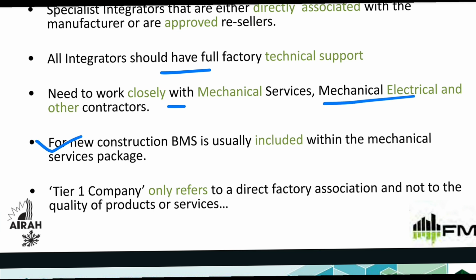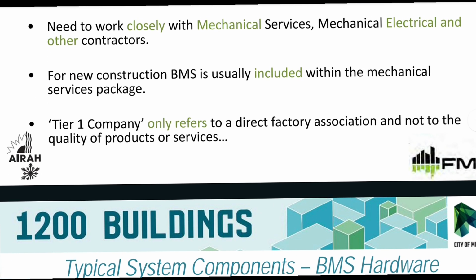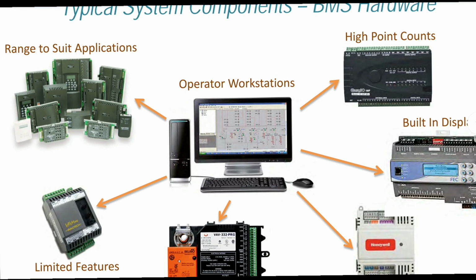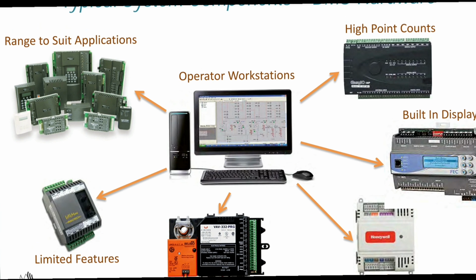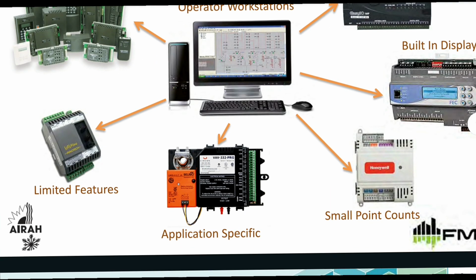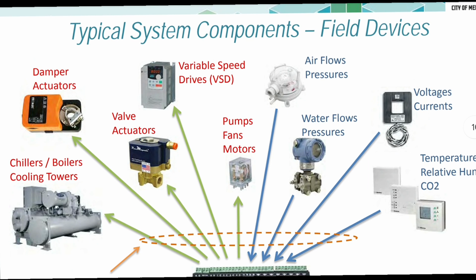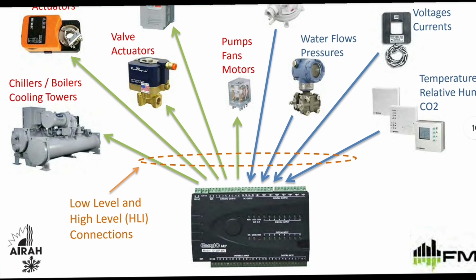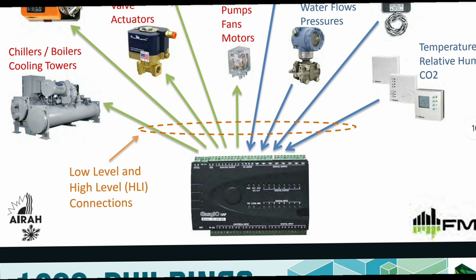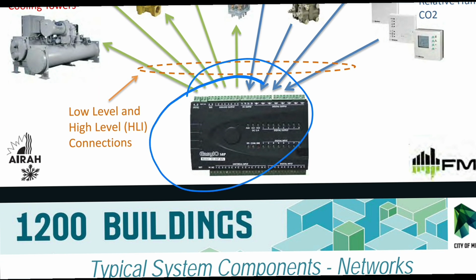For new construction, BMS is usually included within the mechanical services package. Tier 1 company only refers to direct factory association, not to the quality of products or service. Systems range to suit the application, from operator workstations with high point counts to limited-feature systems with built-in displays and small point controllers. Typical system components are field devices like damper actuators, valve actuators, variable speed drives (VSD), air flow and pressure, pump and fan motors, water flow and pressure, voltage and currents, temperature, relative humidity, chillers, boilers, cooling towers, etc.